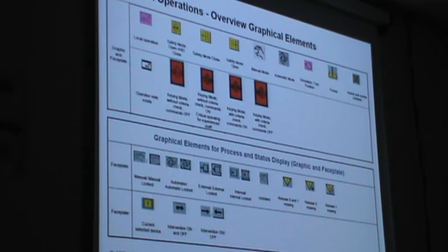And the sequence step modes. This is used to skip or bypass a step in the sequence. If this is selected in the faceplate, you can skip that particular step and enter into the sequence whenever you want. Suppose when you do the backwash, you don't want to do the air scour blower, you can skip that step using these buttons and start the backwash directly.